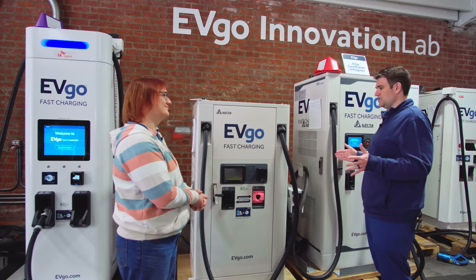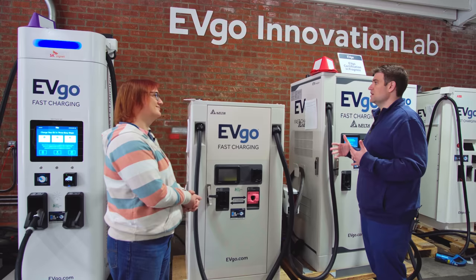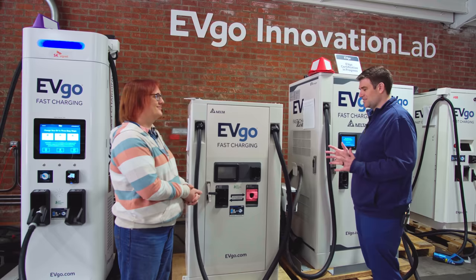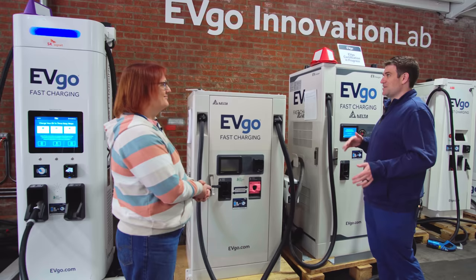We are looking at sites where, if all the charging stations were outputting 350 kilowatts simultaneously, you'd go over the utility service limit — but the number of times that would actually happen is extremely low or almost impossible. So looking at different ways of doing site-level power sharing is really important, not just for us but for every station provider. Because the way charging works today is that power peaks and then comes down, so everybody peaking at the exact same time may not make much sense.